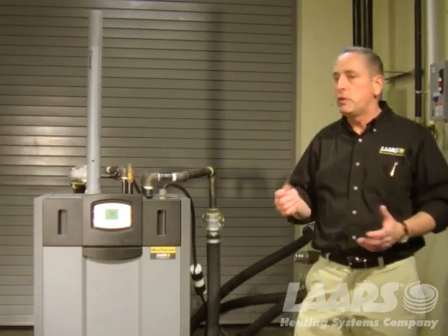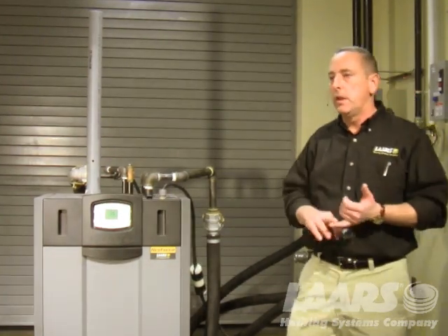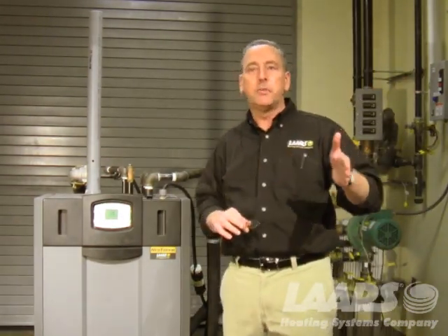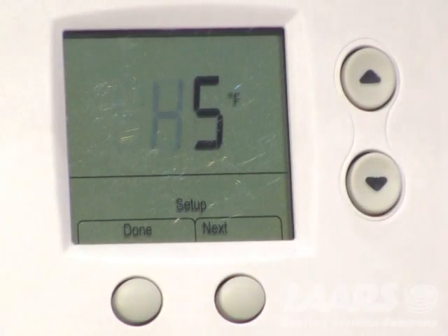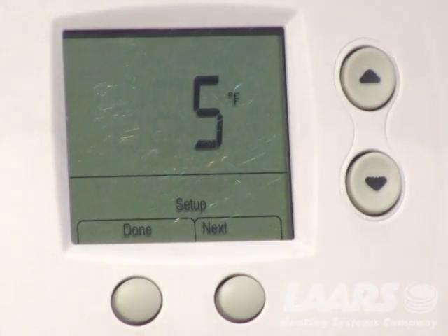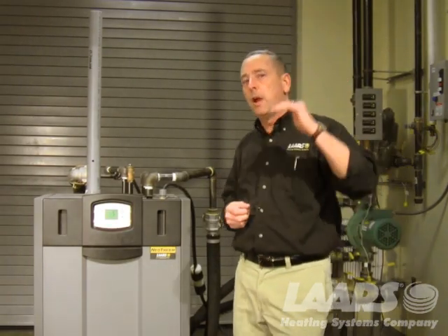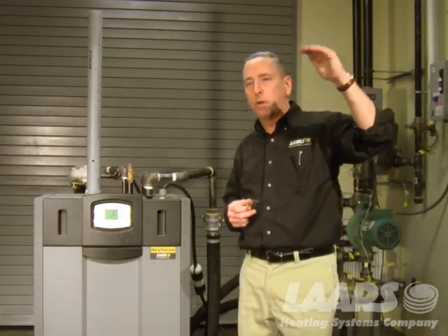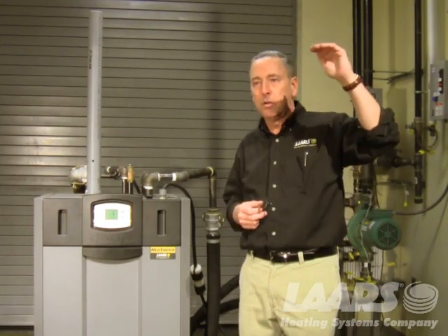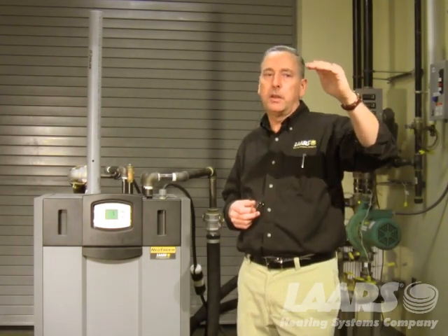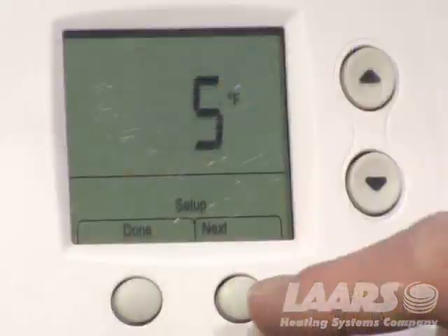Press next again — HS. That's the engineering term for hysteresis, which simply means differential. We have a five-degree differential. Our target was 180 degrees, so the boiler will run up to 185 on the coldest day of the year, and it'll kick back on five degrees below 180 — at 175 degrees it comes back on.